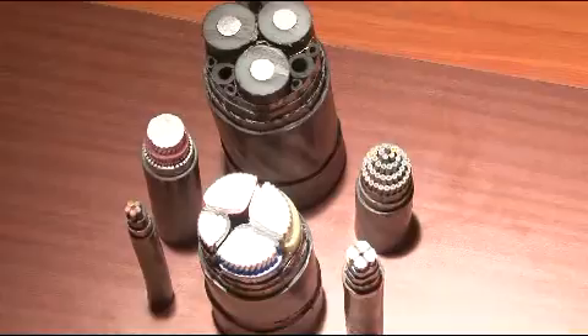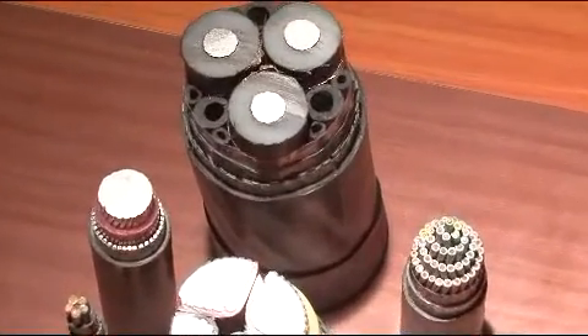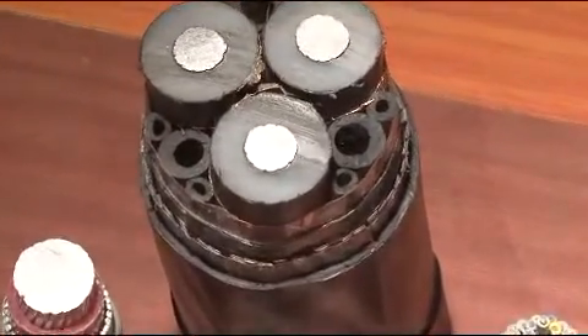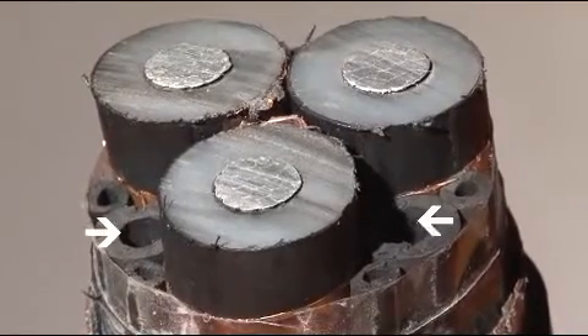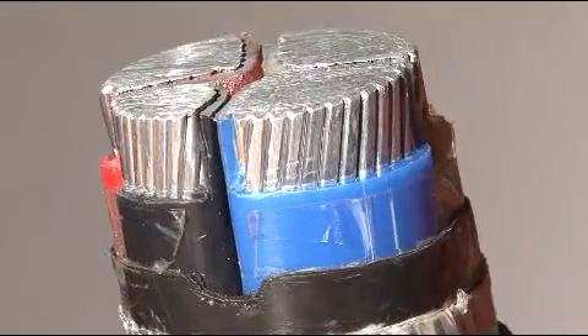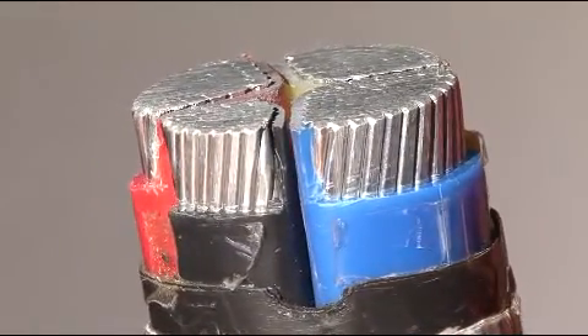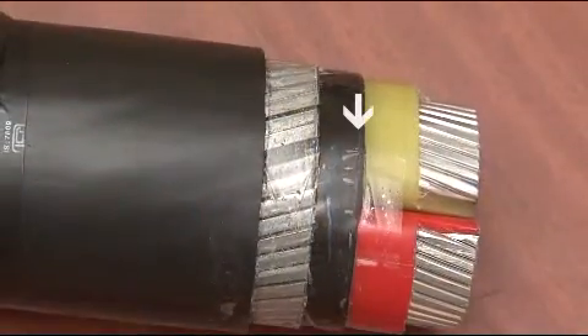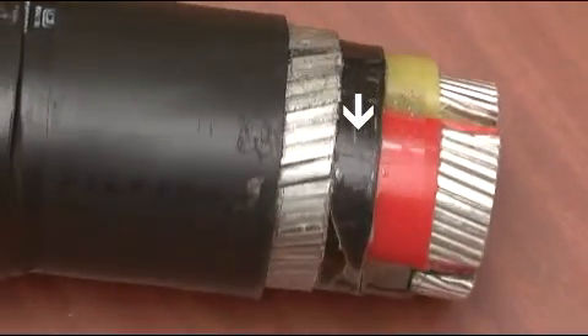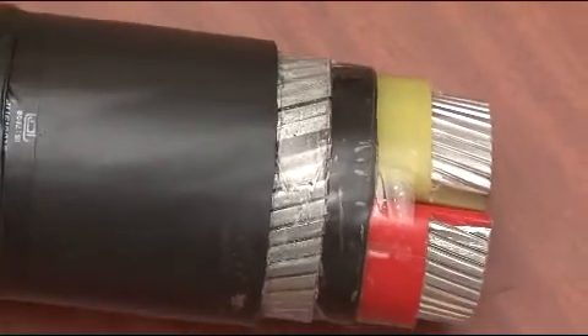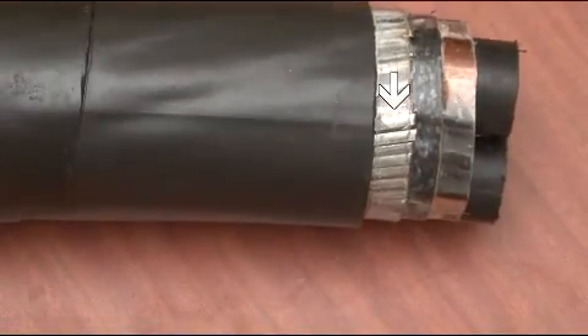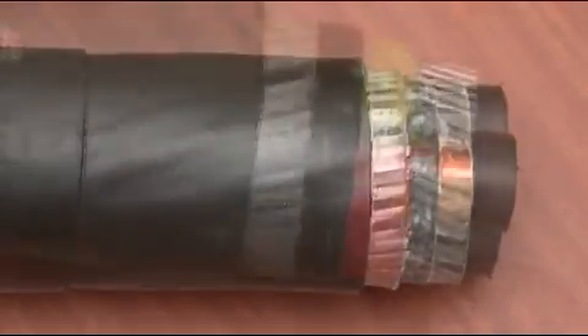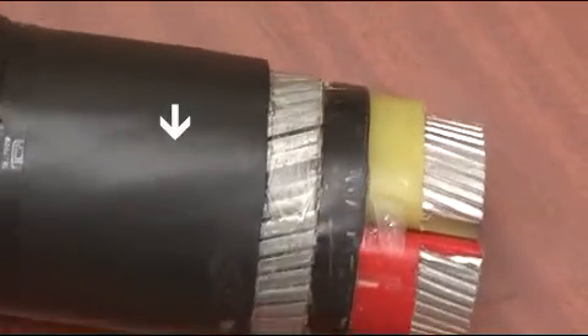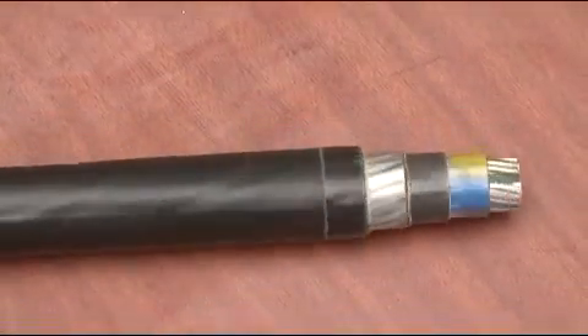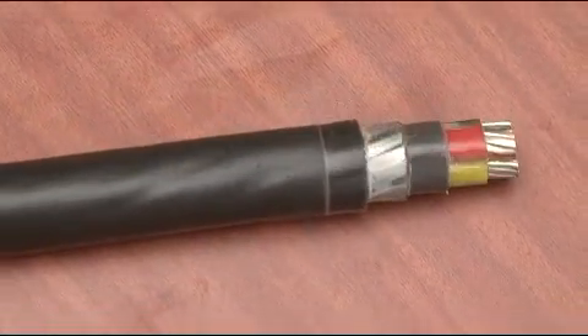XLPE cables. Multi-core cables are laid up as per the color scheme and the interstices are filled up if needed to make the cables cylindrical. All cables with 2 or more cores are provided with a common cover called inner sheath made of PVC compound or thermoplastic. Multi-core cables are provided with armoring, which is made up of galvanized round steel wire over the inner sheath. Outer sheath is extruded over the armoring. This is always black in color to resist the outdoor exposure.